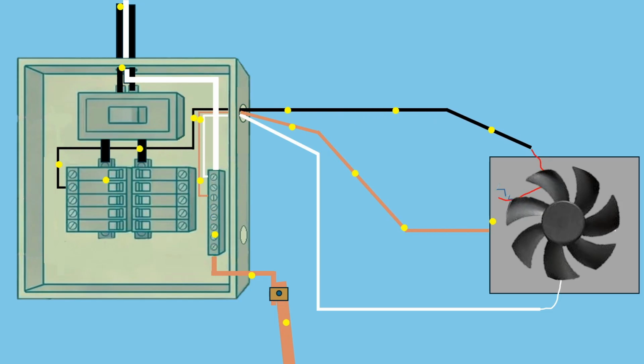So let's follow that path and see what would actually happen if this fault current really did flow down the ground rod. In this scenario, current flows from the loose hot wire to the metal frame of the appliance. From there, it flows onto the ground wire, back to the electrical panel. And then it goes down the grounding electrode conductor into the ground rod and into the earth. Now here's the critical point. The earth has very high electrical resistance compared to copper wire. Because of that high resistance, only a very small amount of current can flow through the ground. And circuit breakers don't trip on voltage, they trip on current.